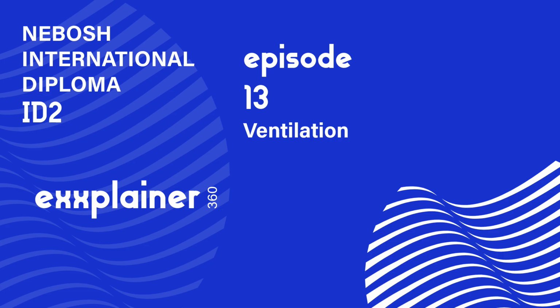Oh, okay. If your discharge stack is too short, the exhaust just gets dumped into this slow-moving boundary layer air. And what happens? It can get sucked right back into the building's fresh air intakes. Defeating the whole purpose, recontaminating the workplace. Exactly. So the stack needs to be high enough to clear that layer, and the discharge velocity, the speed it comes out, needs to be high enough to disperse it effectively away from the building.